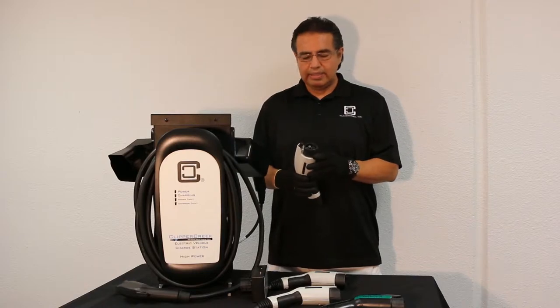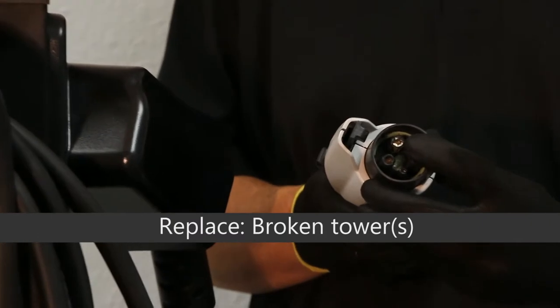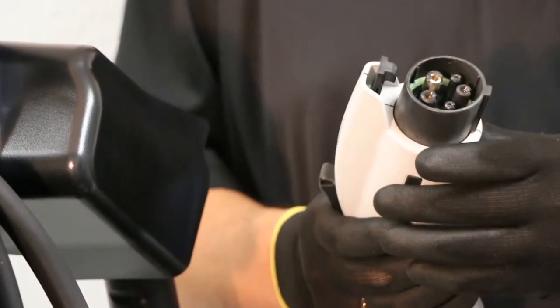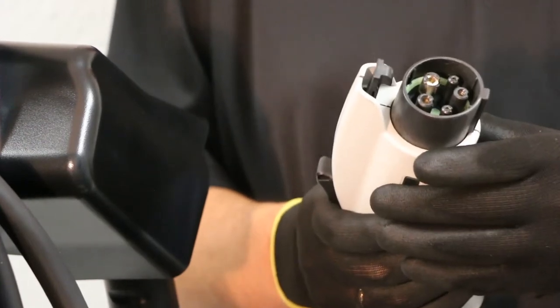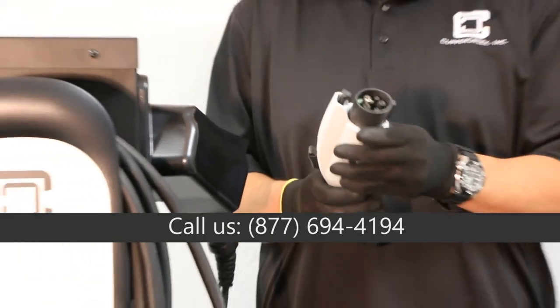Another condition is the towers inside the nozzle being broken. If you look at this one, you can see that the plastic has broken off. It's not a good idea to use the nozzle in this condition — definitely give us a call so that we can replace it.